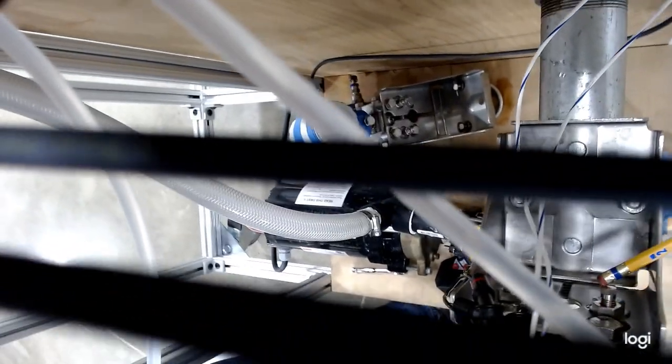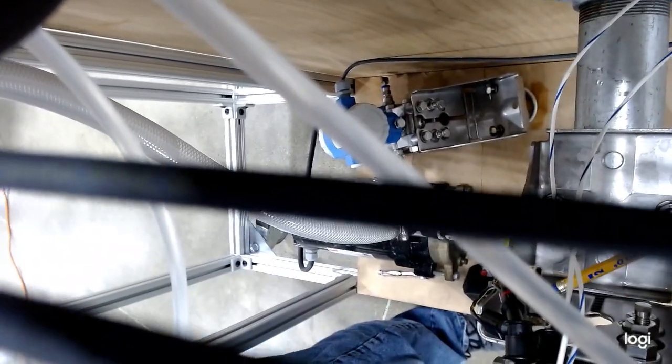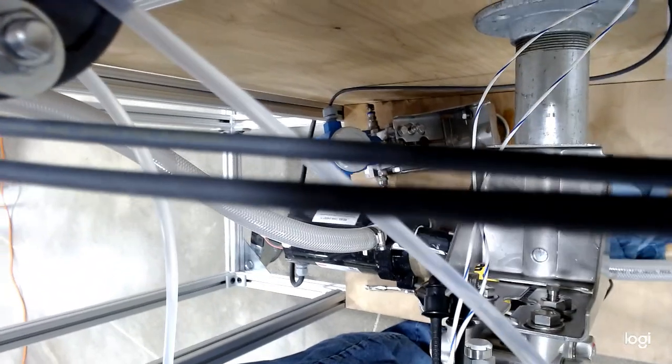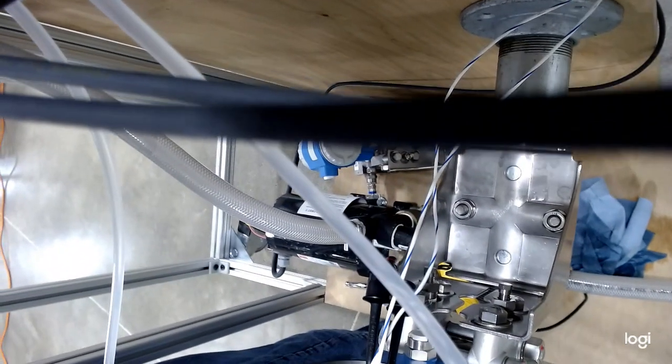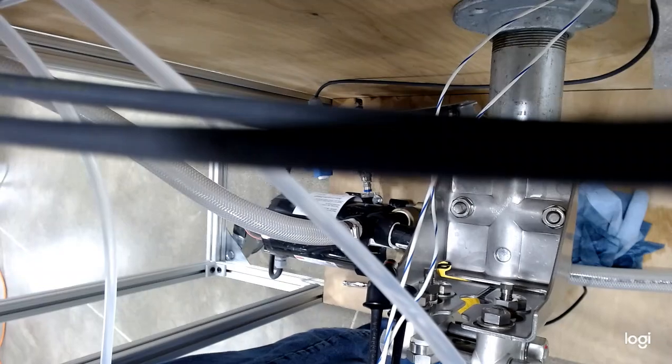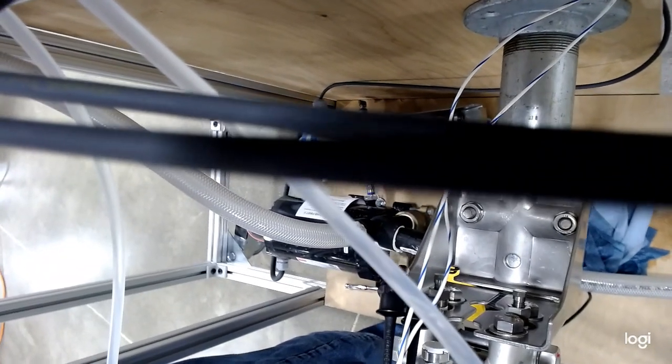If you look back here you can see that there are a couple bleeders here, low and high port bleeders. So what you need to do on them is crack them open and burp them until all the air comes out and all you got is water running out.